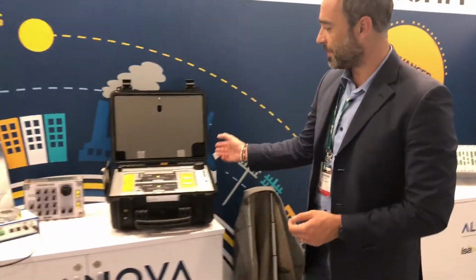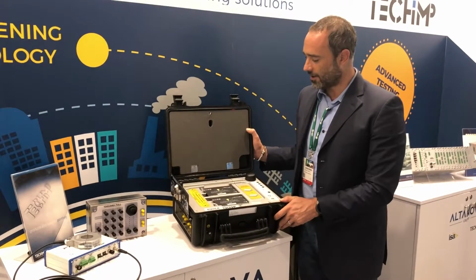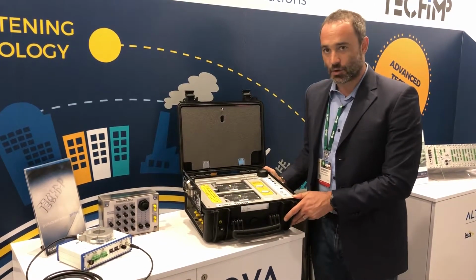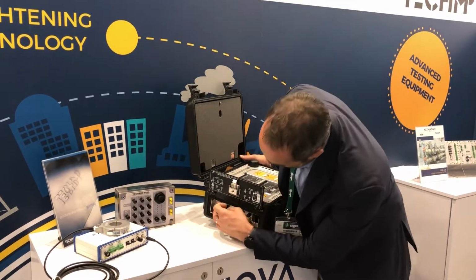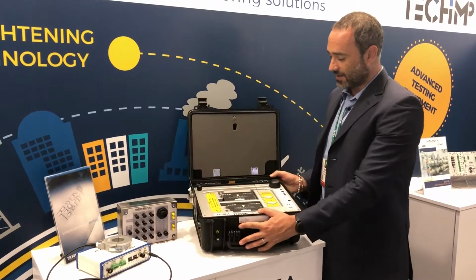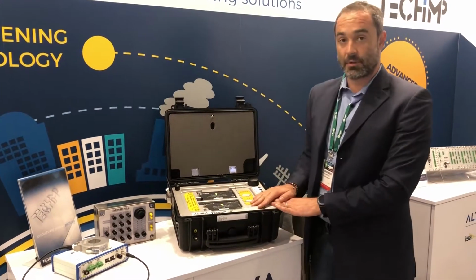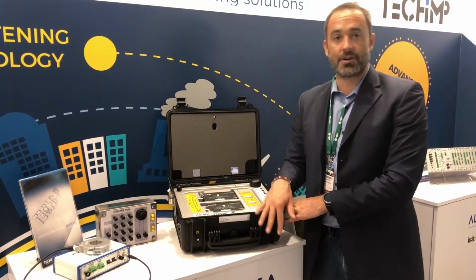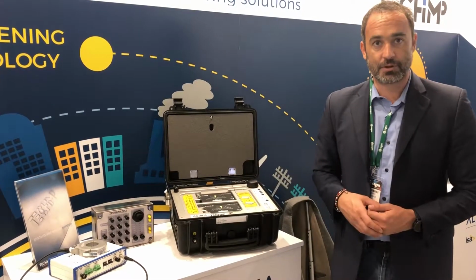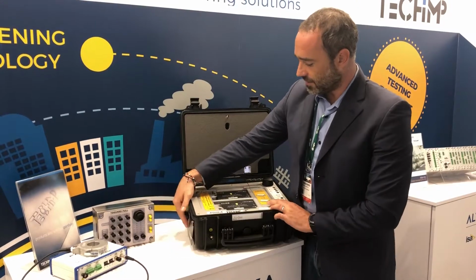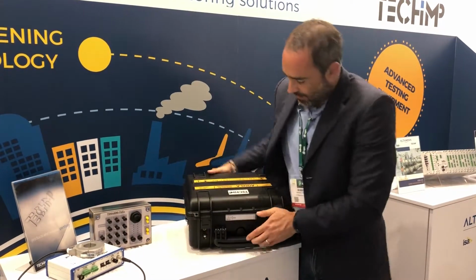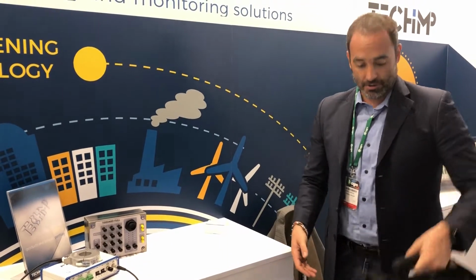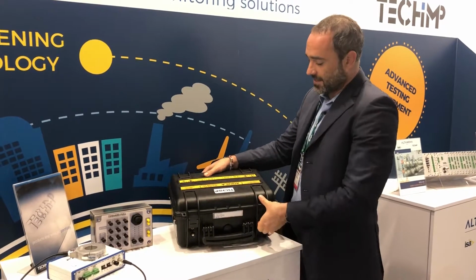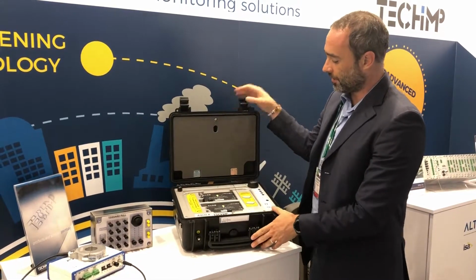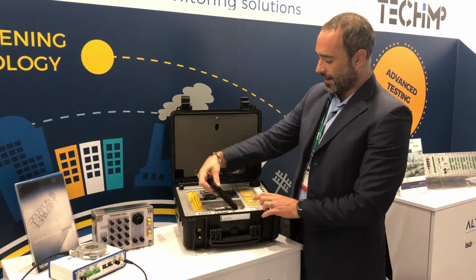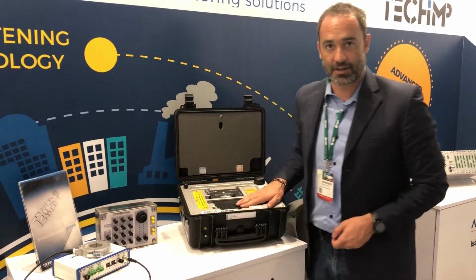Moving on, the Techimp's bestseller, Aquila, or the Eagle, we have here. This is an acquisition unit for PD. So basically, by connecting the sensors here, you can test any asset. This device can be used to test, for example, cables, but also generators and motors, medium voltage switchgear, GIS, transformers, and any other asset that can come to your mind. The device itself is very easy to carry around. When you close it, basically you can carry it easily like a carry-on luggage on an airplane, because it doesn't have more than 10 kilos. And what's also very important, the batteries it uses, they can be put in a way that the device cannot be turned on under any condition.